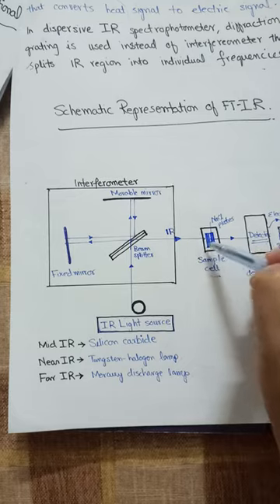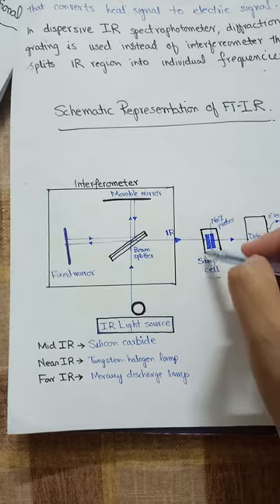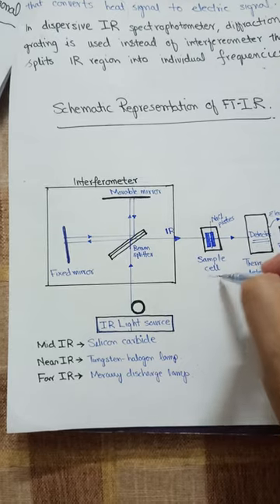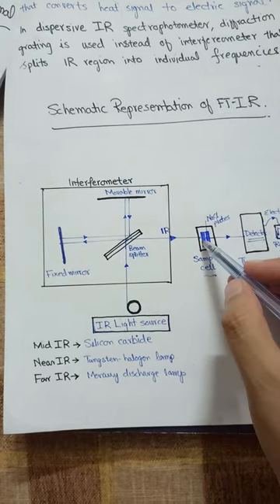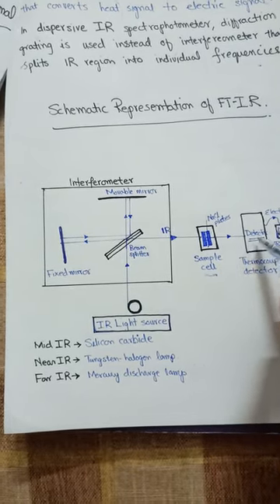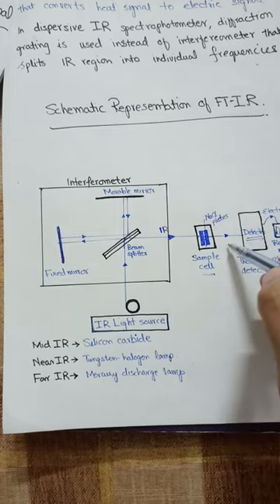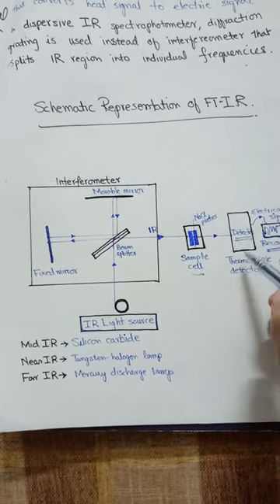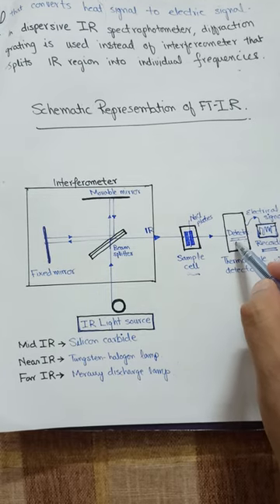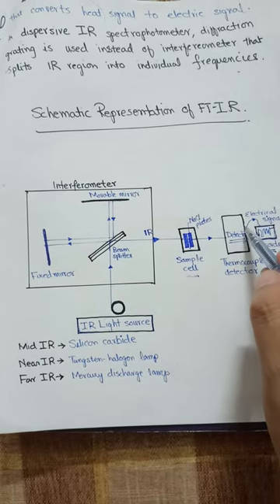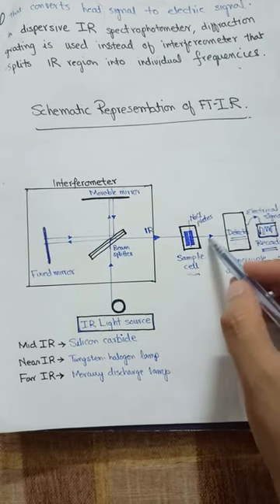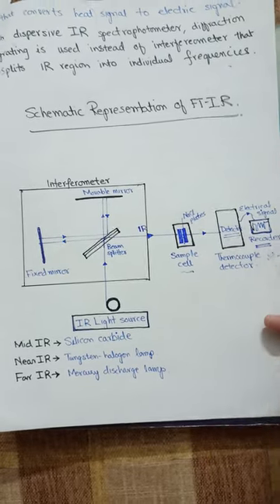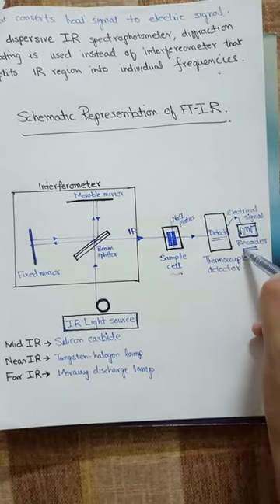The other path goes to the movable mirror, which is adjusted so that constructive interference is produced. These IR radiations then fall on the sample in the sample cell. After absorption of the radiation, the beam falls on the detector, which detects the signal in the form of electrical signals — converting IR radiation into electrical signals recorded as a spectrum.